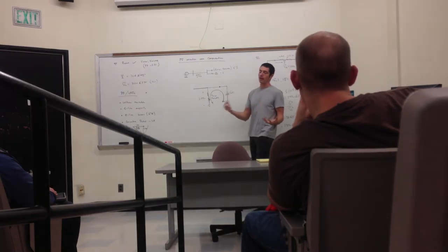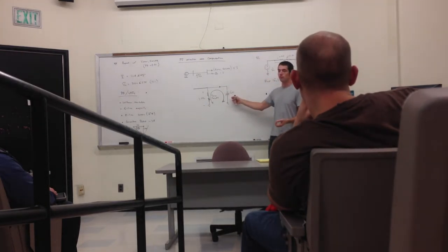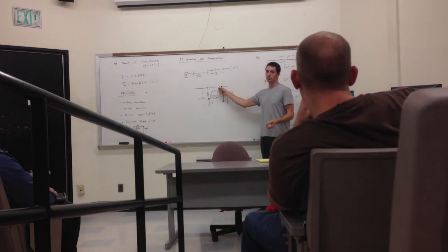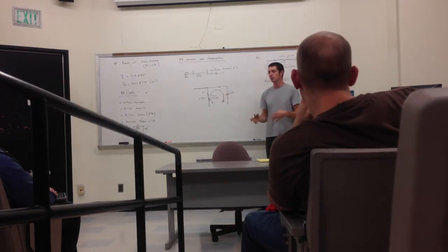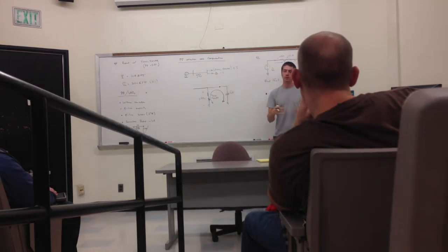You make an economic decision about whether to install it. If so, you put it in at the service entrance, not at the individual machine. So typically, the machines themselves don't come with compensation capacitors tied into them, but rather that's done by the facilities engineer based on an economic analysis of this versus that.